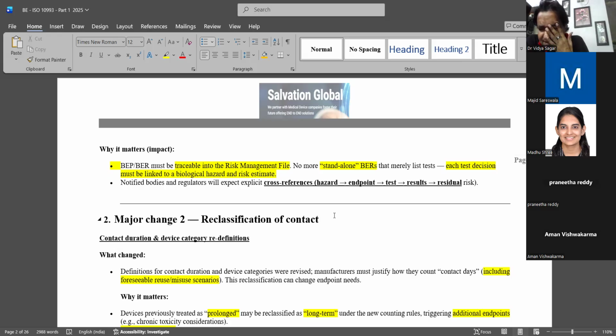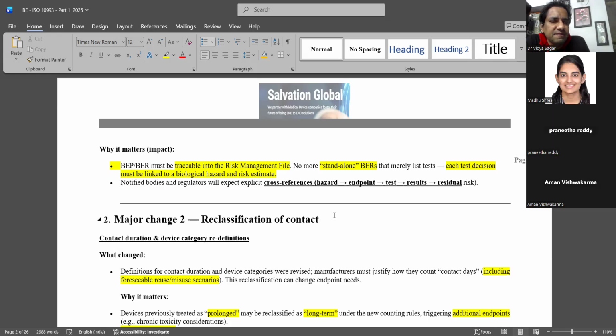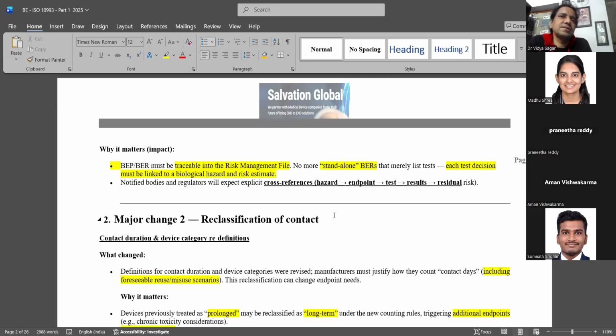And the other thing, when you are working on the residual risk, is a very crucial point that people in design and development understand. There will be some parameters or some design inputs. If you reduce the safety, it may directly correlate or link with the performance also. Suppose if you are reducing the safety, the performance also comes down.